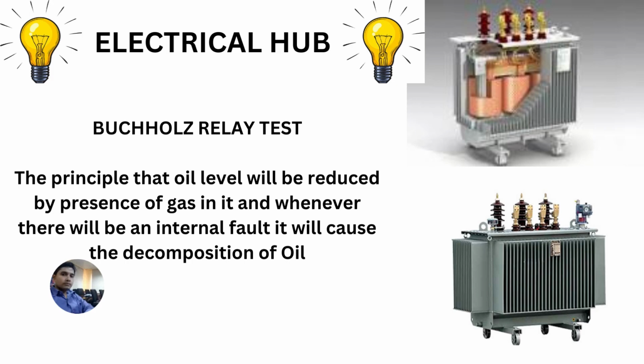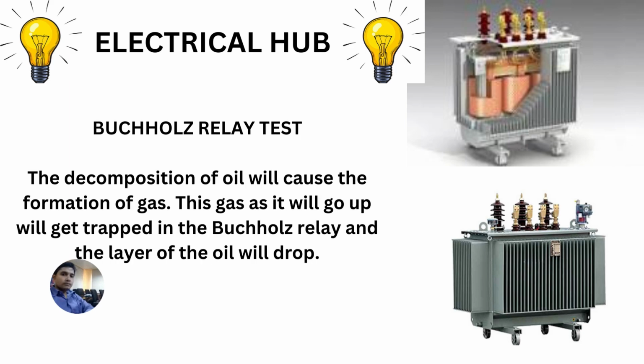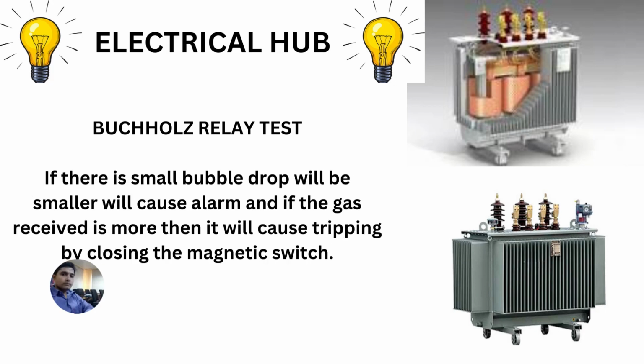So we can check the Buchholz relay in a similar way. As we know, the decomposition of the oil will cause the formation of gas, and the gas will go and get trapped in the Buchholz relay. So what we can do is reduce the level of the oil in the Buchholz relay by isolating and draining the oil. Thus, we can get the alarm and the tripping.